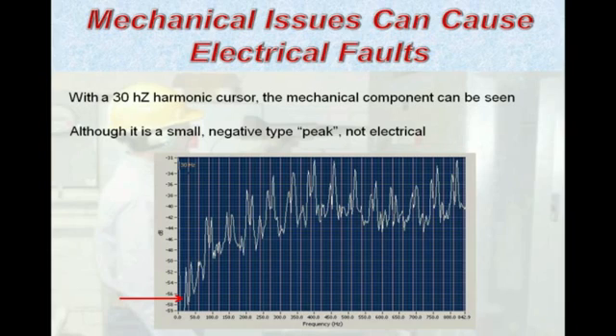The other thing is turning the 30 Hz harmonic cursor on is an important analytical step. And you can see where the red arrow is pointing, there is a peak, although it's on the negative side, I call it the negative side, at 30 Hz. One of the key indicators that we have a mechanical issue, not an electrical issue. When we're dealing with electrical, you will never have a faulting frequency below your line operating frequency if it's electrical in nature. We can see this is half of the operating frequency of 60 Hertz, which now points to a mechanical issue.